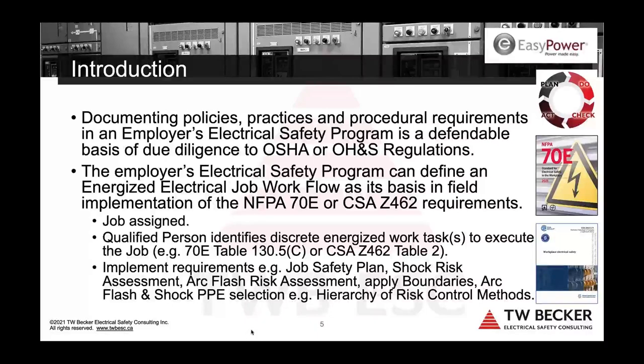And we want the worker to then apply these additional protective measures, the boundaries, and the arc flash and shock PPE, and other risk control methods, so that when they do this at-risk work, again, we've either eliminated exposure or the qualified person has personally reduced their risk of exposure to as low as reasonably practicable.